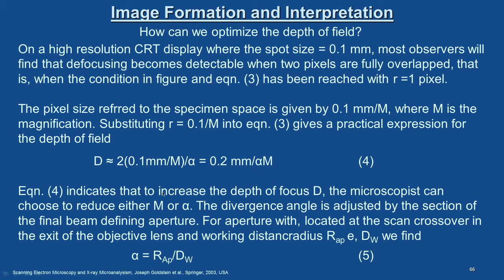This equation indicates that to increase depth of field D, the microscopist can reduce either M or α. Normally we are interested in higher magnification, so the divergence angle α is adjusted by selecting the final beam-defining aperture. For an aperture with radius R_ap located at the exit of the objective lens at working distance D_w, we find α = R_ap / D_w. This expression shows how one can optimize depth of field in SEM.